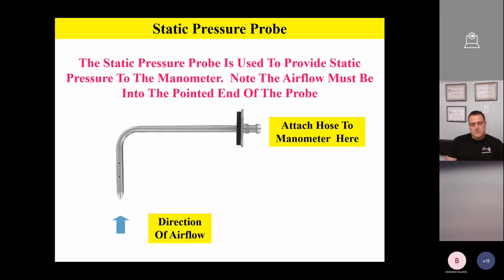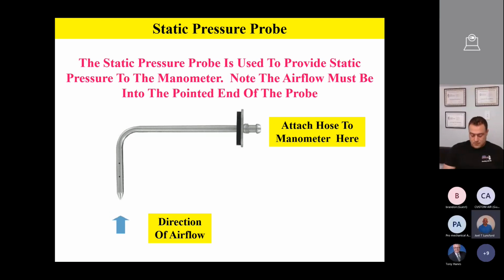The other end of the static pressure probe is going to be hooked up to a hose that goes to the manometer. So basically, you're going to have your digital manometer with a hose going to this static pressure probe. You'll poke a hole in the ductwork. You'll poke a hole in the supply plenum and the return plenum. And then you'll actually read the static pressure or the pressure of the return and the supply air.